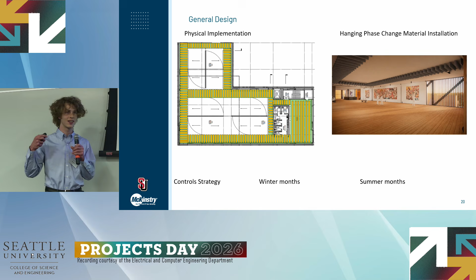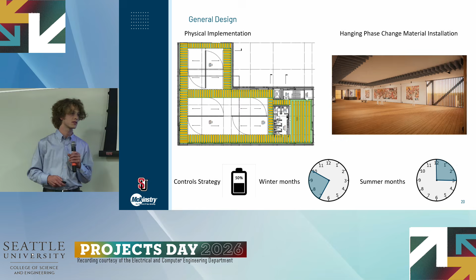The phase change material will be contained in these baffles. As the temperature in the gallery rises, the material melts, absorbing heat; as it lowers, the material freezes, rejecting heat, lowering strain on the HVAC systems. We also propose a control strategy limiting HVAC capacity to 50%, from 7 to 10 in winter months and from 12 to 3 in summer months, coinciding with peak grid stress hours.